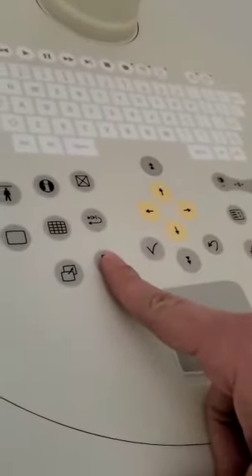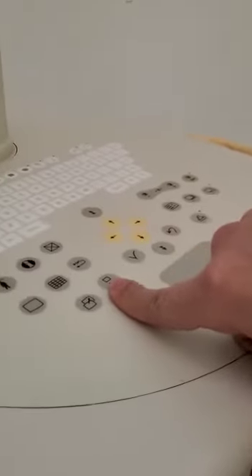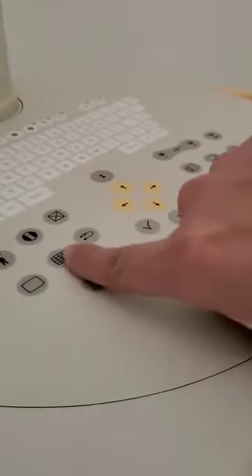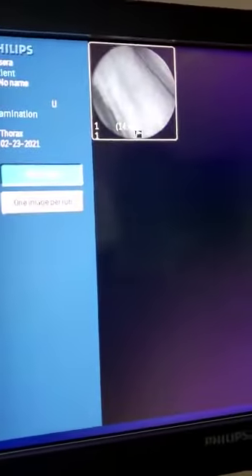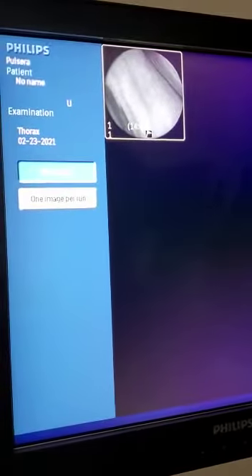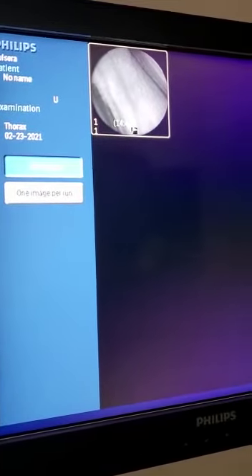Okay. The second button you need to know, which is found on the remote and the workstation, is to protect an image. So it saves all the images under high definition fluoro. So anytime you hit the right foot switch or you hit the right hand switch, you're going to save an image. But to make sure it's not deleted, you can always protect the images you want, in the overview especially. So if you hit the overview under review, pretend there's 50 images here as you're scrolling through. The fastest way to sort through all these images is to flag the 3 or 4 that you like and then delete. What's unique about Philips, it deletes all the images at once. So if you hit delete, it will delete them all.